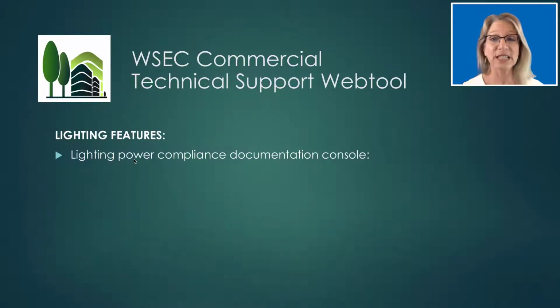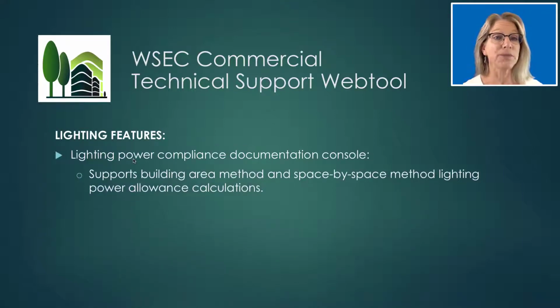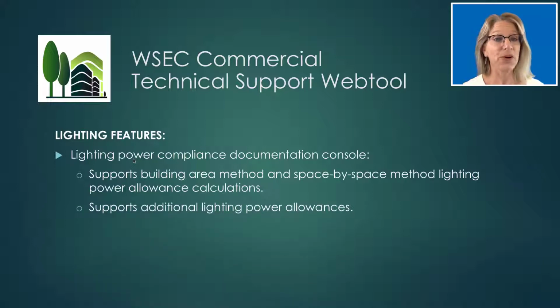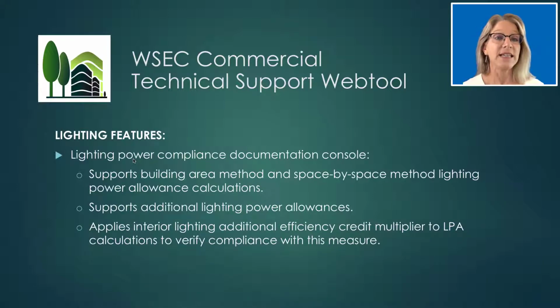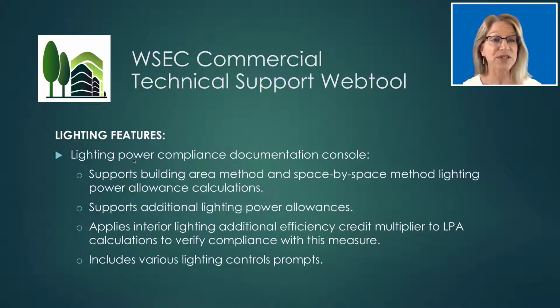So specifically for lighting, we have developed a lighting power compliance documentation console. This feature supports the building area method and the space-by-space method lighting power allowance calculation. It supports additional lighting power allowances, those are the ones we talked about just a few moments ago. It applies the interior lighting additional efficiency credit multiplier to LPA calculations to verify compliance with this measure. And it includes various lighting controls prompts.